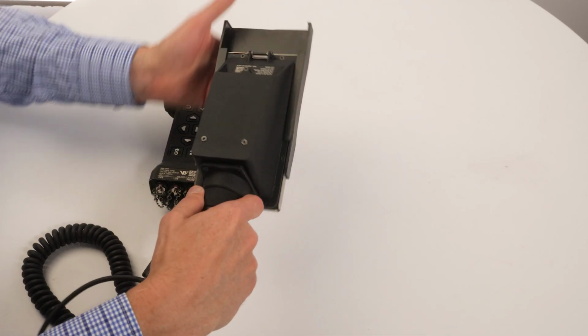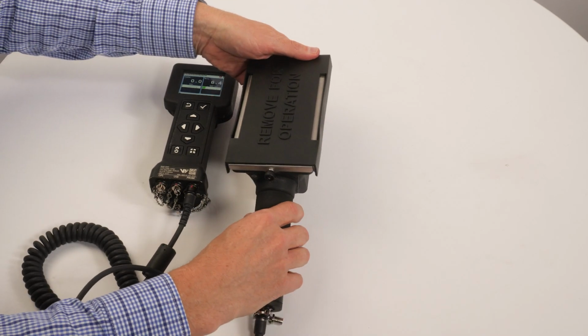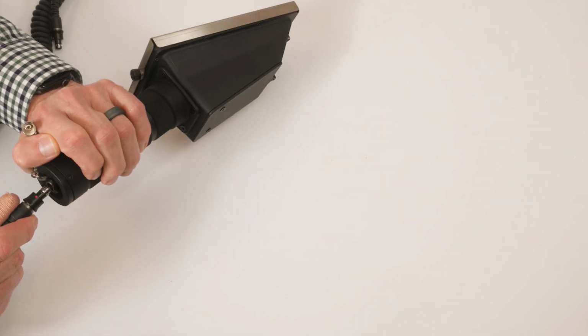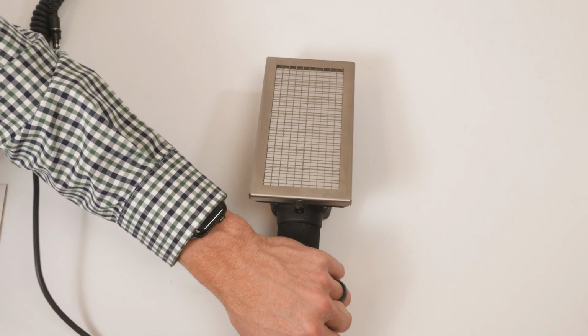Install the alpha beta probe protective cover by sliding it on the front of the probe. Allow the probe at least 2 hours to dark adapt, which means the scintillator needs to take time to settle after being exposed to light, even from light leaks from very small holes, prior to plugging it into the base unit and powering it on. The probe must pass a source check before being returned to service.